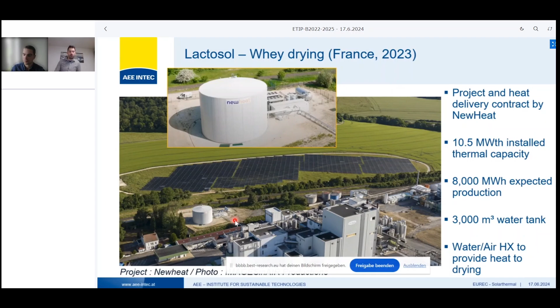Solar thermal has a very low levelized cost of heat in the right environment. We see successful examples with quite low levelized cost of heat, around 20 to 40 euros per megawatt hour, for projects with quite low renewable fraction. This graphic shows it as a function of renewable fraction from around 25% up to 100%. Solar thermal can hardly be a 100% solution, except with very large storage and so on, but it's a cheap, easy to implement, and efficient solution in both land area used and energy, that can be part of the mix together with increased storage size and combination with heat pumps and other solutions.